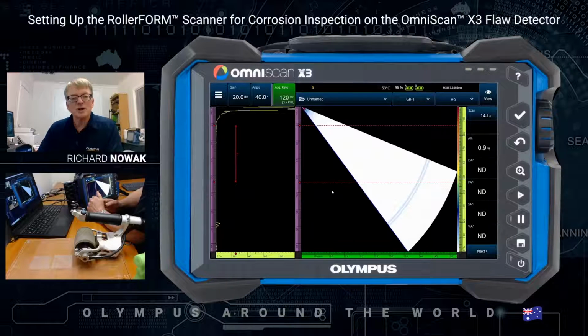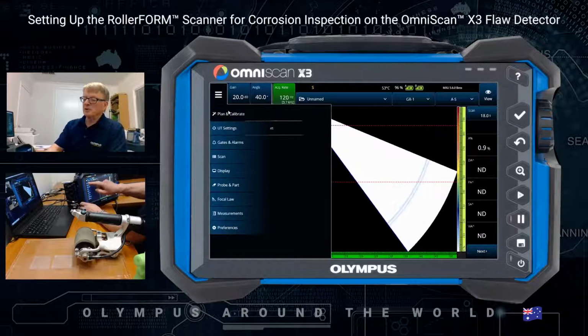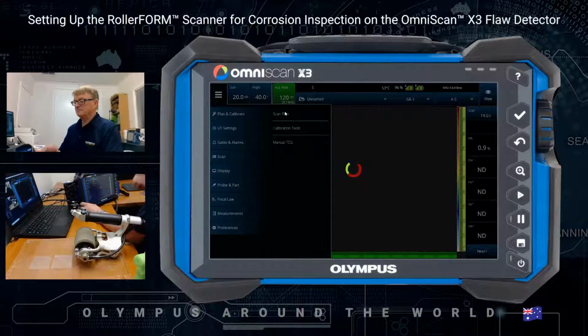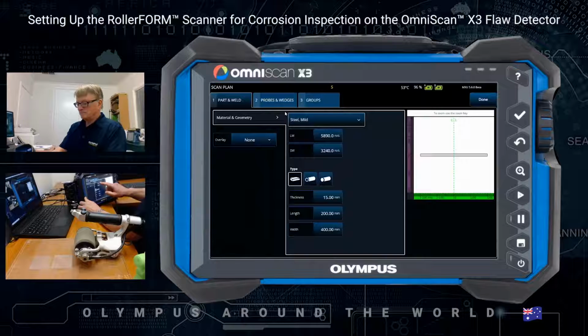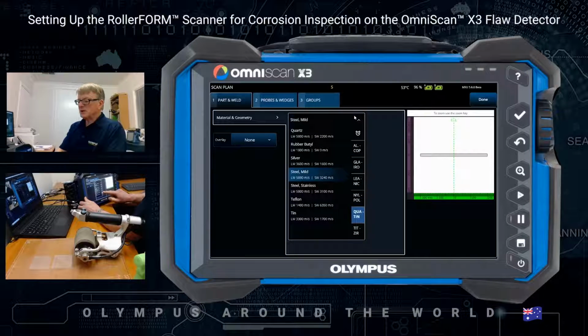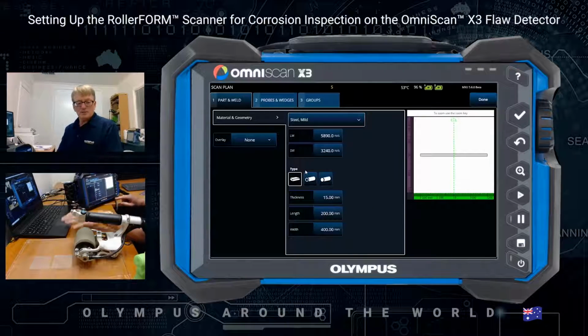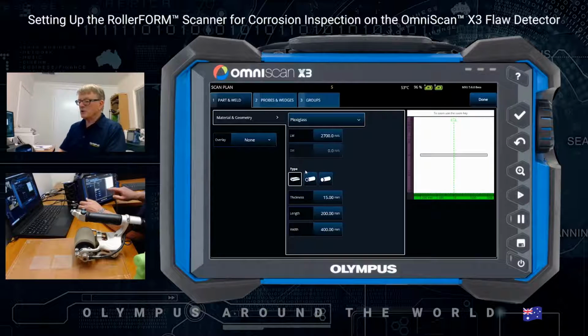It's my pleasure to show you how to set up corrosion on the OmniScan X3. Let's begin with plan and calibrate. I have a plexiglass plate, this one here with some simulated corrosion in it. There is a procedure here. You can use the calibration to determine the velocity. If you know the velocity, you can just punch it in here.